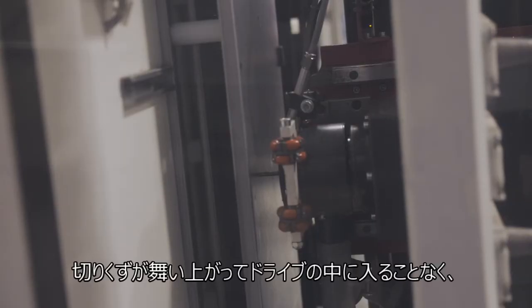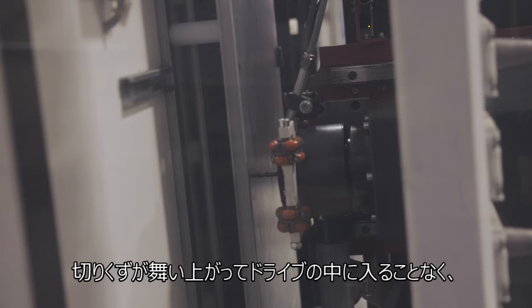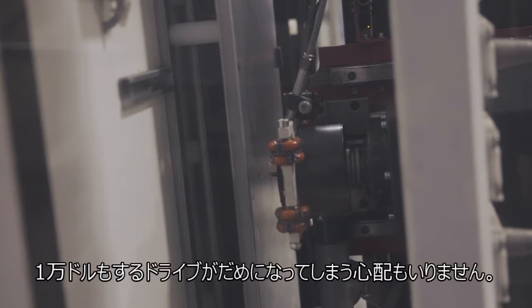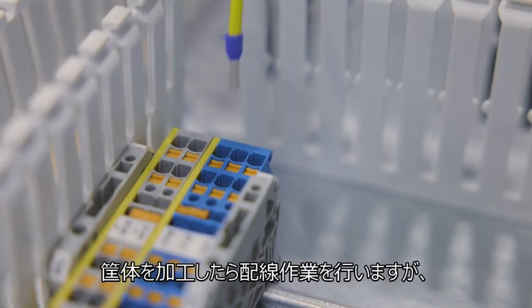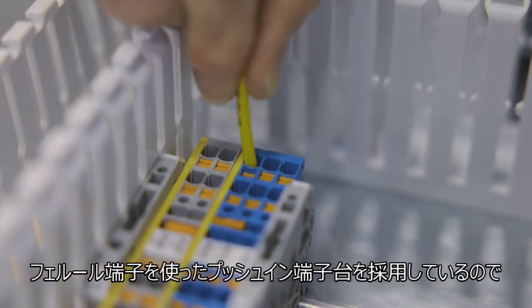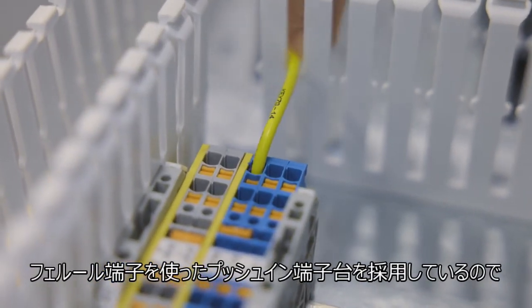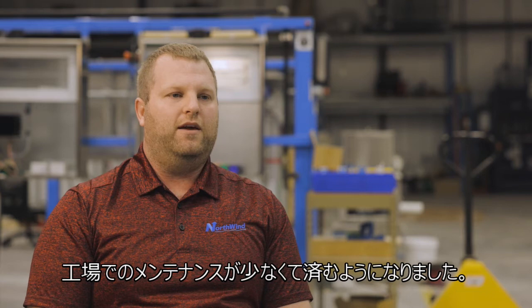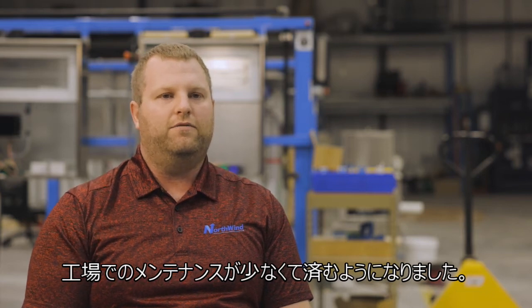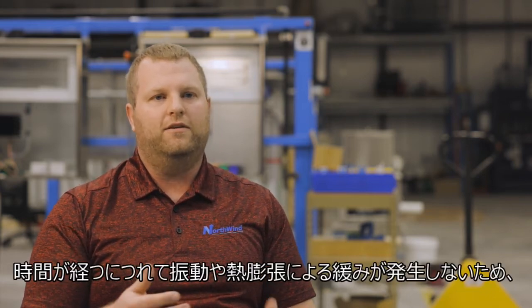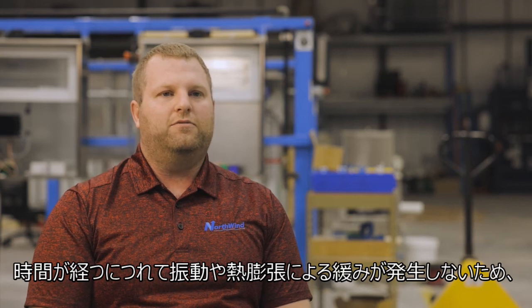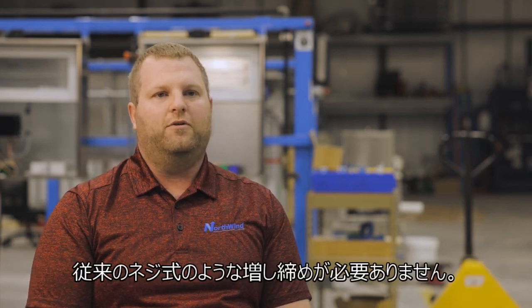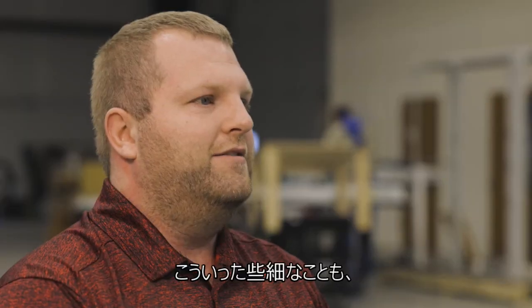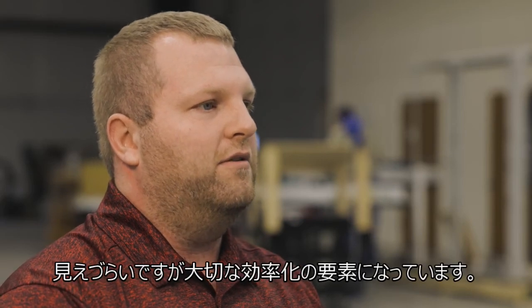There's no chance of ever having one of those fall into the top of your drive and then blow up a $10,000 drive. And then you go all the way down to like the push-in terminal. You pair those with ferrules, and now a plant doesn't have as much maintenance later on. They don't have things that are loosening up over time as you have those interactions with vibration and thermal expansion or whatever. I mean, all that stuff is the unseen benefits that someone is getting out of all this.